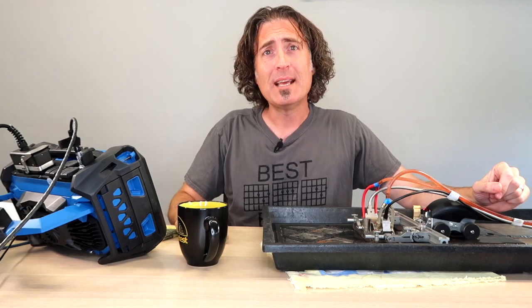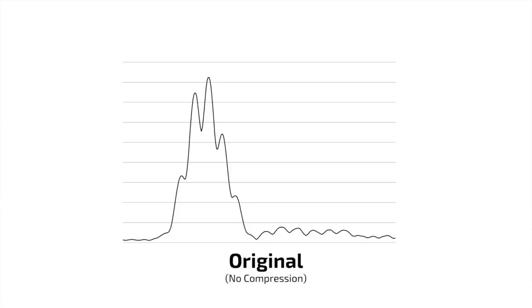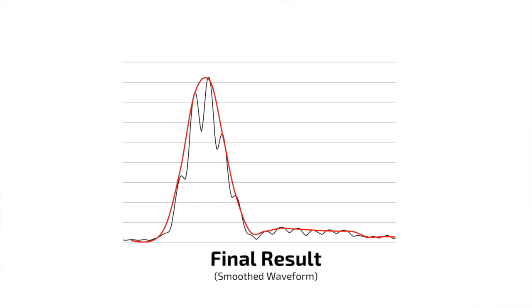Points Quantity sort of resamples the A-Scan into X number of points. It's not a pure resampling. What it does is actually kind of clever. It takes the A-Scan, divides it into that many bins that you have defined in your Points Quantity, and then takes the highest amplitude it sees in each bin and then uses that for each value.